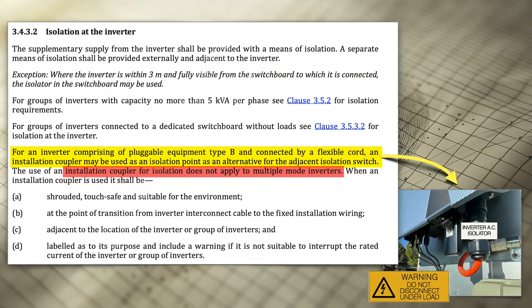Okay, what does this mean? Well, you don't need an AC isolator right next to your inverter. Your installation coupler is your means of isolating the AC. Given that if you turn off the inverter supply main switch at the switchboard, there's no current flowing, and so unplugging this is not under load and does then provide isolation. So that's a good thing, one less isolator.